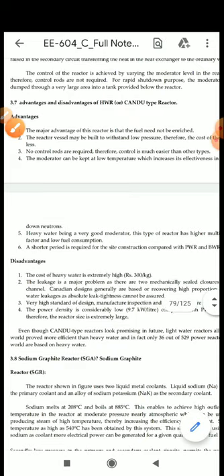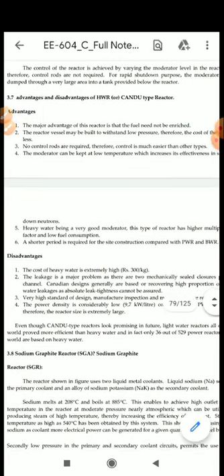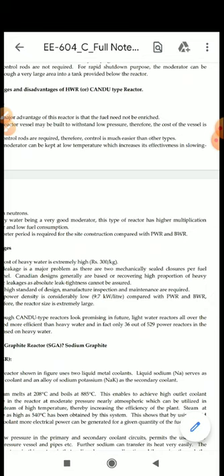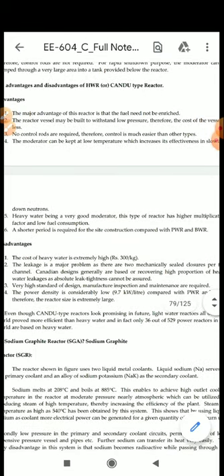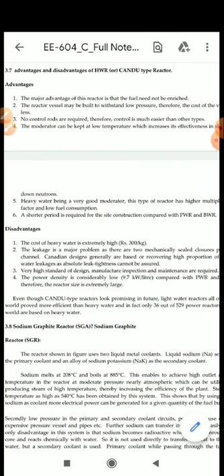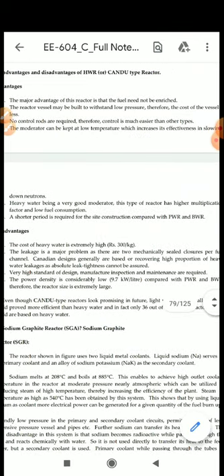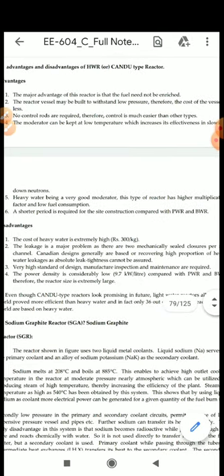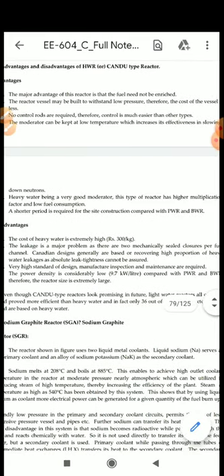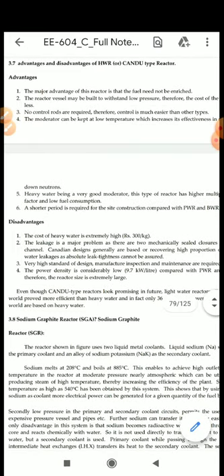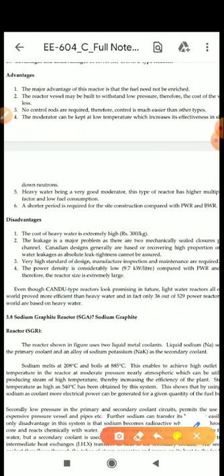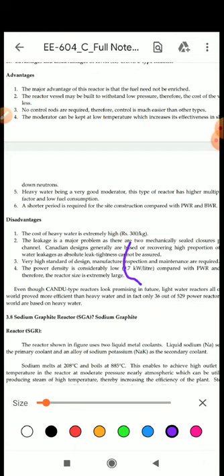The second disadvantage is the leakage is a major problem. Therefore two mechanically sealed closures per fuel channel are required. Canadian design generally is based on recovering high proportion of heavy water leakages as absolute leak tightness cannot be assured. The third disadvantage is very high standard of design, manufacture, inspection, and maintenance are required. The power density is considerably low which is around 9.7 kilowatt per liter.